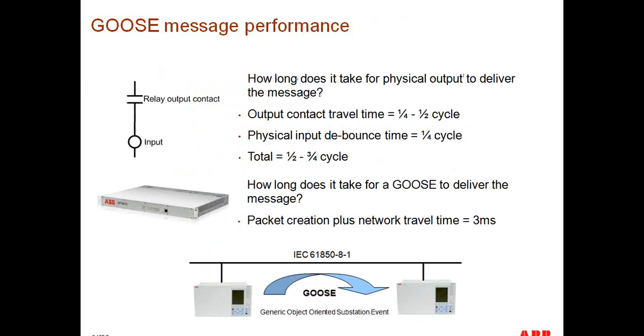GOOSE message performance, as we discussed, is very comparable to hardwired output contacts, and the math is pretty simple. The output contact travel time is anywhere between a quarter of a cycle to half a cycle, and I emphasize again, these are not solid-state output contacts that I'm assuming, but ice cube relays, which is what most protection relays utilize. So just the travel time of that output is anywhere between a quarter to half a cycle.